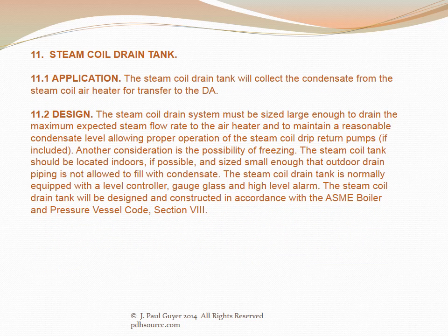With regard to steam coil drain tanks, the steam coil drain tank will collect the condensate from the steam coil air heater for transfer to the deaerator. The steam coil drain system must be sized large enough to drain the maximum expected steam flow rate to the air heater and to maintain a reasonable condensate level allowing proper operation of the steam coil drip return pumps. The steam coil tanks should be located indoors if possible, sized small enough that outdoor drain piping is not allowed to fill with condensate. The steam coil drain tank is normally equipped with a level controller, gauge glass, and high level alarm, and will be designed and constructed in accordance with the ASME boiler and pressure vessel code section 8.